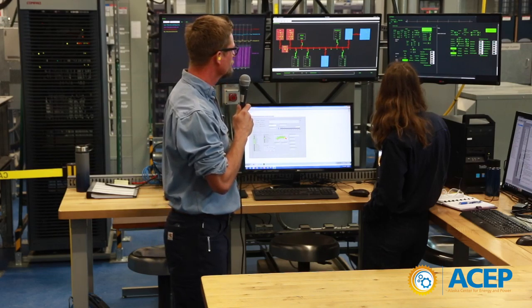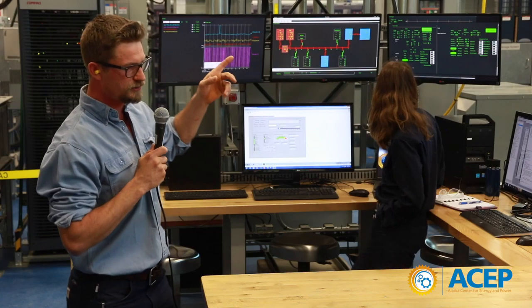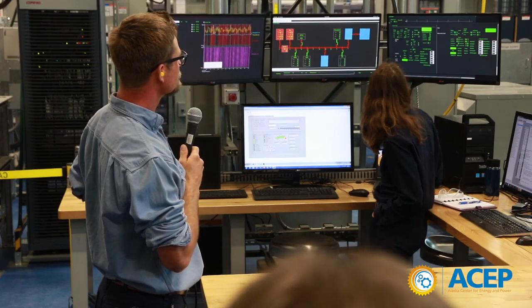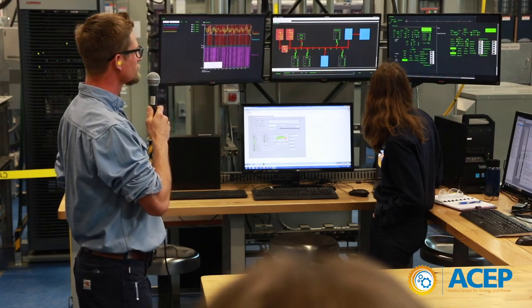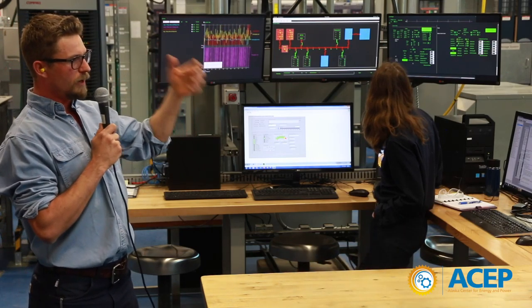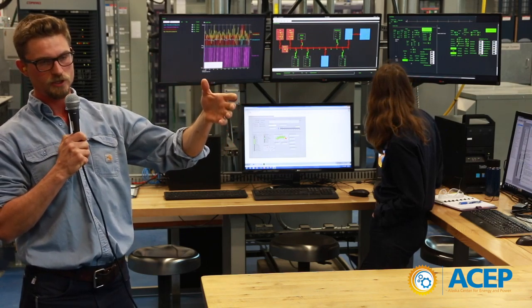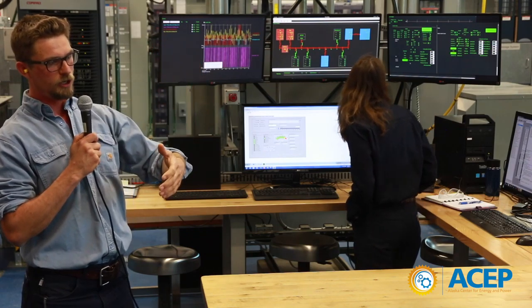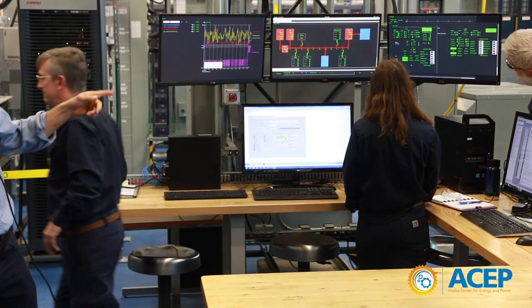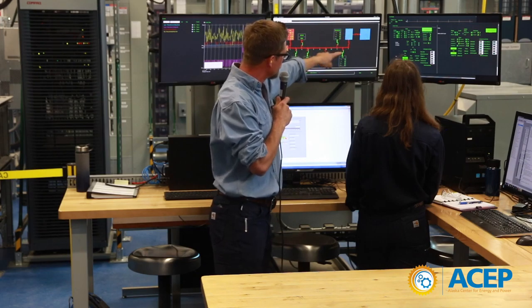Let's start it up. There are going to be two loud bangs — two circuit breakers have to close to energize our battery system. The first one closes on the DC bus and connects our DC bus; the second closes the inverter onto the AC bus. The second one needs to synchronize first — everything needs to synchronize with the grid. There's the first bang. We've closed the battery system to the inverter, and now the inverter is closed to the grid.